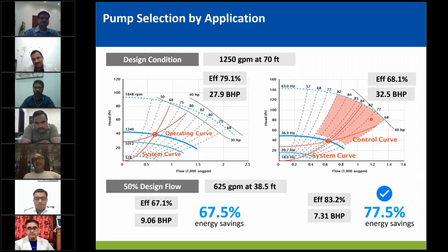So in this case, we are selecting the pump to be on the right hand side of BEP at full duty point, and then when we slow it down, we fall into the best efficiency point, and because of that, the part load efficiencies are higher compared to the left hand side way of selecting, and it not only achieves ASHRAE 90.1 requirements but exceeds that requirement. So it gives you 77% energy savings in this example. So it makes sense to select variable speed pumps differently, especially when it comes to secondary or variable primary applications. They all tend to operate 24 hours a day, and in our region, that's why it saves a lot of energy just by selecting it differently.